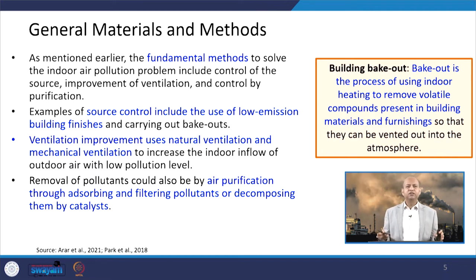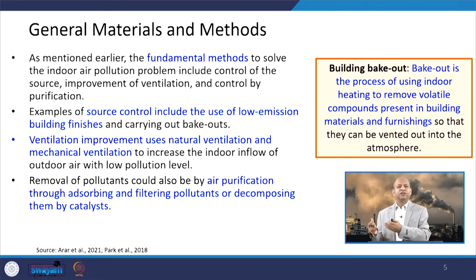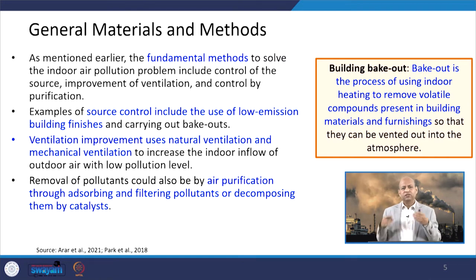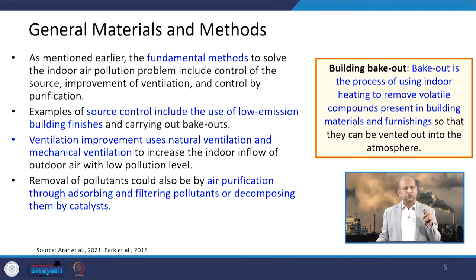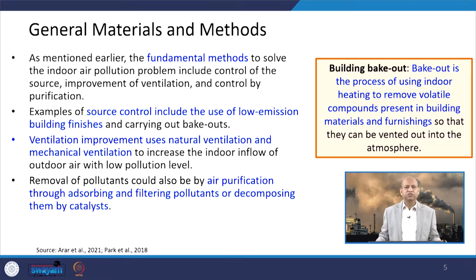When discussing general materials and methods to improve indoor air quality, three major approaches exist: ventilation, source control, and purification. To control emissions at the source, low-emission building finishing materials can be used — since furniture and wall paints are major sources of indoor air pollutants — or bakeout procedures can be applied, where the indoor environment is heated to drive out VOCs (volatile organic compounds), resulting in very low emissions afterwards.